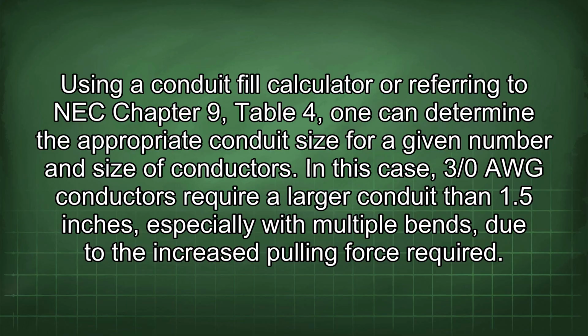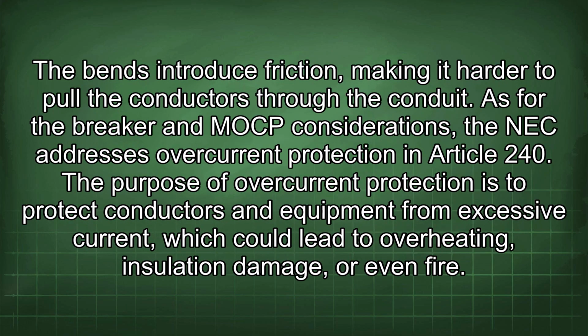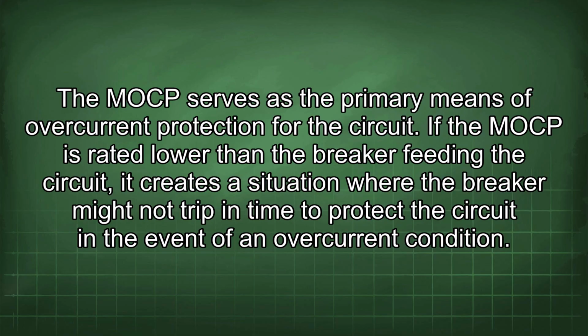In this case, 3/0 AWG conductors require a larger conduit than 1.5 inches, especially with multiple bends, due to the increased pulling force required. The bends introduce friction, making it harder to pull the conductors through the conduit. As for the breaker and MOCP considerations, the NEC addresses overcurrent protection in Article 240. The purpose of overcurrent protection is to protect conductors and equipment from excessive current which could lead to overheating, insulation damage, or even fire. The MOCP serves as the primary means of overcurrent protection for the circuit.